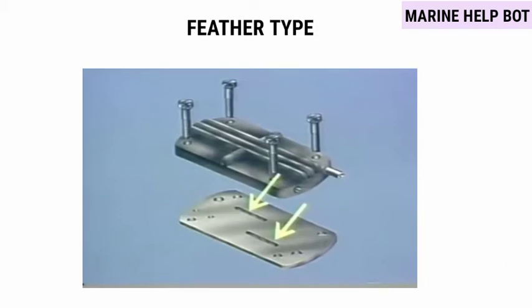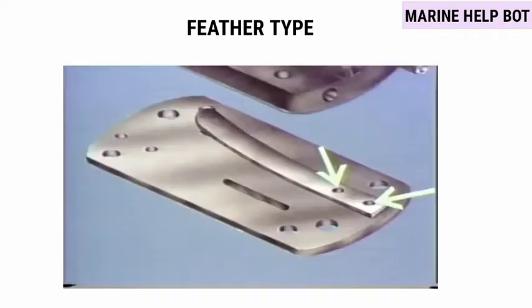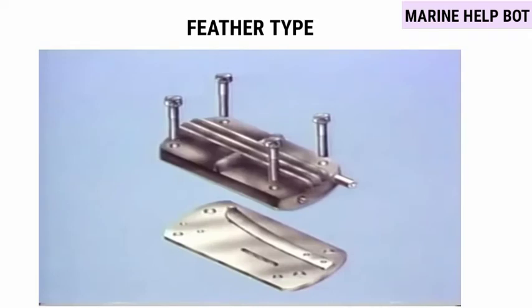In the feather type valve, suction and discharge are on a single plate. On both suction and discharge sides there is a riveted strip. The suction side valve strip is on the downside and the discharge side valve strip is on top. When suction occurs, a vacuum is created and the strip provides space to let air into the cylinder. When air is compressed, the discharge side valve strip provides space to let air go out to the receiver side.